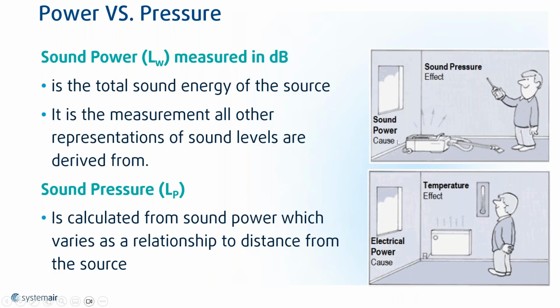Sound power is what we call the root cause of the sound, and sound pressure is the effect it has. Sound pressure is calculated from sound power, and varies as a relationship to distance. It's equivalent to saying the electrical power is the cause of heat, and the temperature is the effect, depending on the room conditions, how far you are, etc. So it's super important when we deal with sound that we look at sound power when judging the room. And you're going to see with our solution, we can give you the raw sound power, so any acoustical consultant or acoustical engineer can go in and help make sure that class is as quiet as it can be or should be.